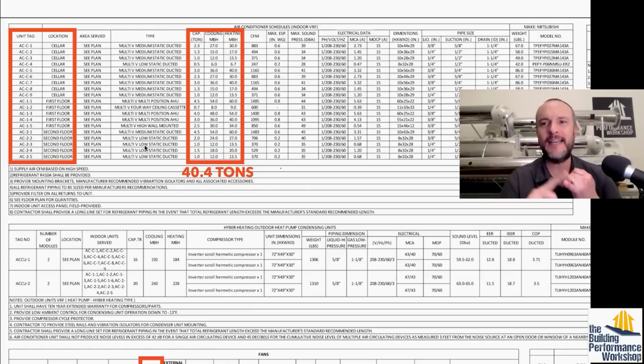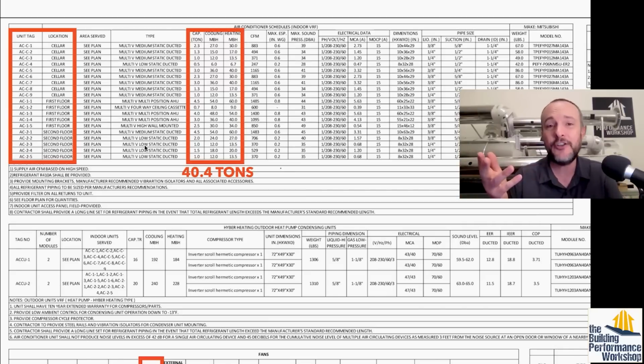And it also builds in equipment, which in the case of commercial spaces would be restaurant fridges or cooler cases or lit up cabinets for putting jewelry in, things like that. All that gives off heat. It's also going to assume that in each of these rooms there are like 10 or 14 people, because they're building it for what happens at rush hour when your store gets packed with people, all waiting around for you to become available, hanging out on their phones and just giving your space heat. So all those things are being built into a home design like this, and they just don't apply.